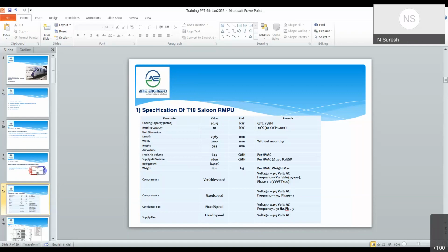Yeah, the cooling capacity is approximately 29 kilowatt at 50-degree ambient and 13% RH. Heating capacity is 10 kilowatt. It's exactly 9 kilowatt. And the dimension of the unit is 2.5 meters length, 2.1 meters width, and height is 0.45 meters. And the fresh air volume is 645 cmh, and the supply air volume is 3600 cmh. The refrigerant used in the system is R407C, and the approximate weight of the unit is 800 kg.